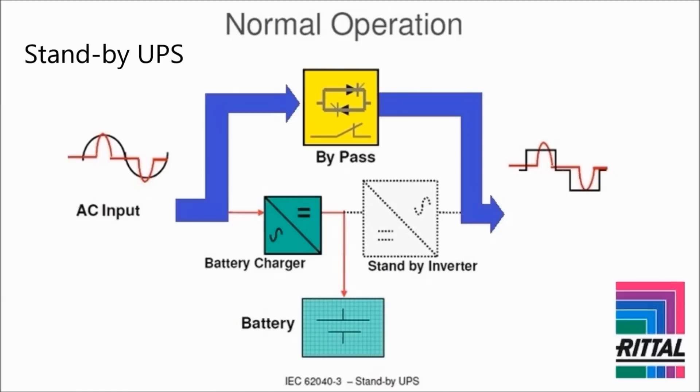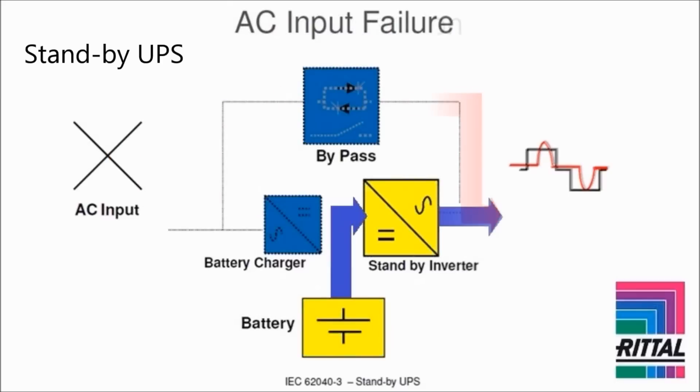The standby or offline UPS has a square wave output, which is often referred to as a modified sine wave output. When utility power is available, it is supplied to the connected equipment through a bypass switch, and the AC input is simply passed through to the output. When the AC input fails, the battery-powered inverter outputs a stepped square wave, forming a crude approximation of a sine wave output.